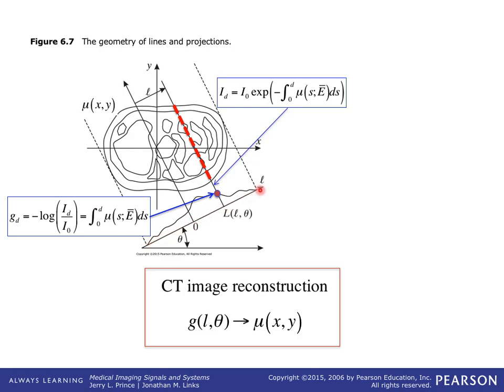There are about a thousand detectors along one dimension. We click through a certain number of angles — you want about the same number of angles as detector points, roughly a thousand angles, actually about 800 on most modern scanners — in order to solve for a pixel with a resolution of about half a millimeter by half a millimeter. Our raw data is a two-dimensional function of L along the detector and theta for each different view, and we invert or solve for the underlying mu(x,y) field given this data.